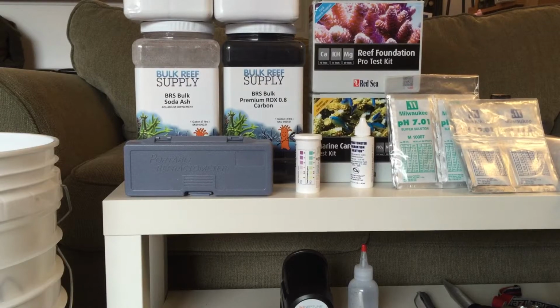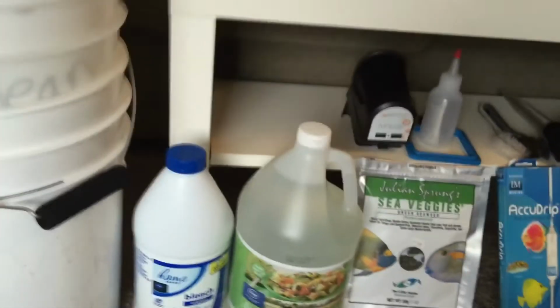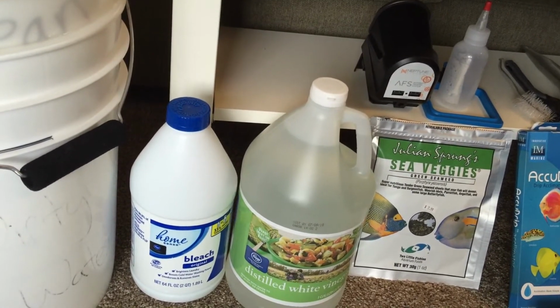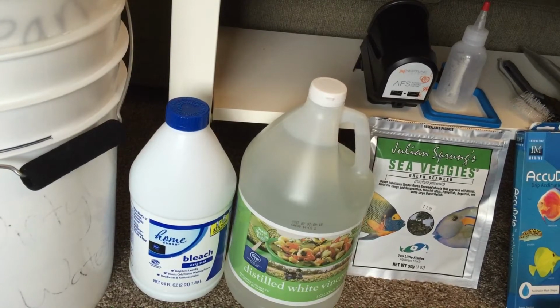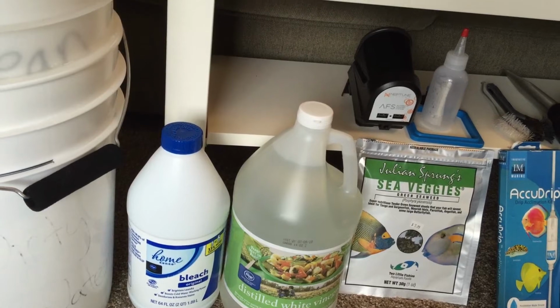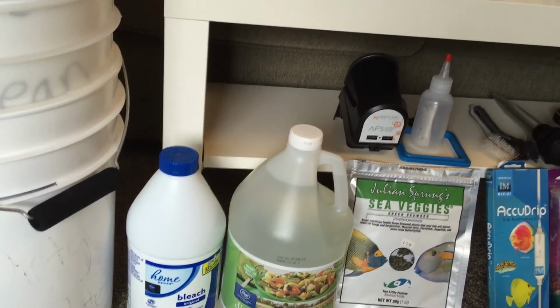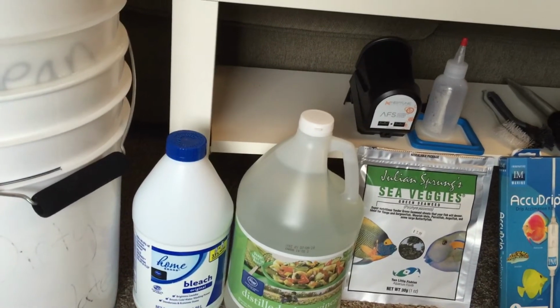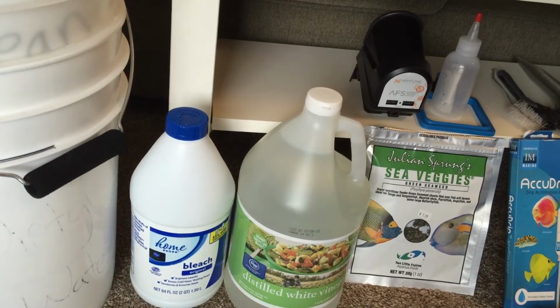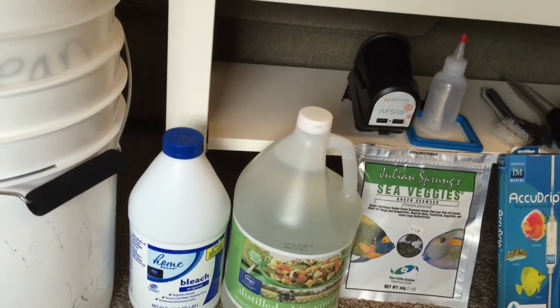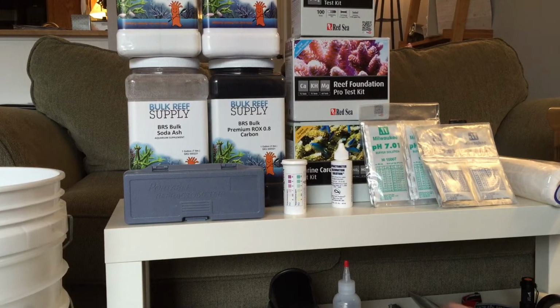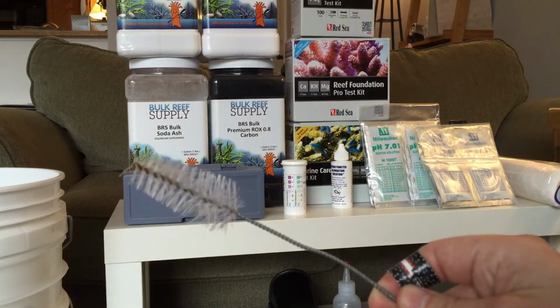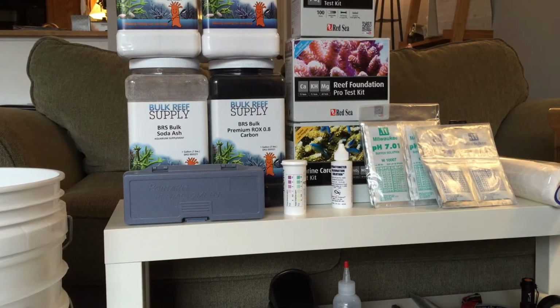Semi-annual maintenance, once every 6 months: clean all pumps and power heads, and that's where vinegar comes in. Plain white vinegar is the acid you'll use to clear off calcium buildup. Take them out and soak them in 1 part vinegar to 5 parts water, although you can add more vinegar to make it quicker, then scrub everything down so your pumps last longer. Just buy a bunch of cheap white vinegar for this. Also clean your tubing and pipes—you can use longer wire brushes, or take them off and soak them in vinegar as well, since there's calcium buildup there too. Just remove any calcium buildup you see on your equipment.